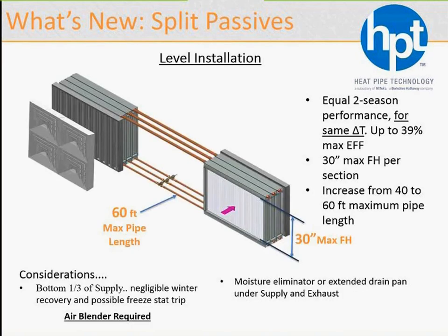I'm sorry, I hit that button too many times. Similar to the previous product, the wraparound heat pipes, extended drain pans will be needed on the downstream side of those heat exchangers. So the extended drain pans or moisture eliminators would be required.